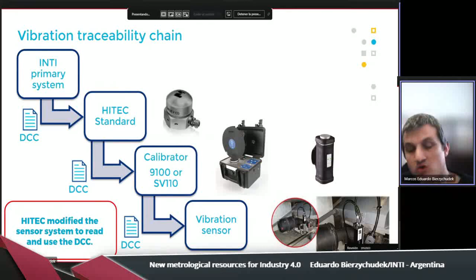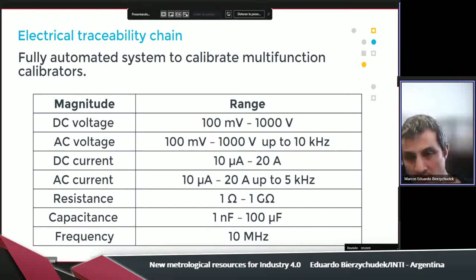The other traceability chain where we are working is the electrical traceability chain. Our objective is to create a new automatic system for the calibration of multifunction calibrators. In the signal that you can see here, the magnitudes are DC and AC voltage, DC and AC current, resistance, capacitance, and frequency. As you can see in the AC voltage, we don't try to cover all the range of the multifunction calibrator. We work in a reduced range, but this range is the most important for the industry.